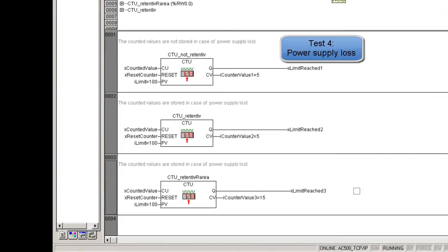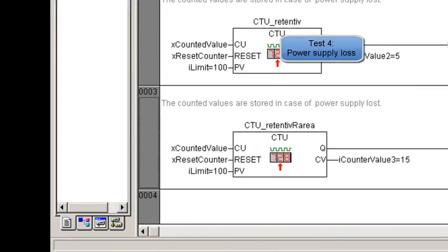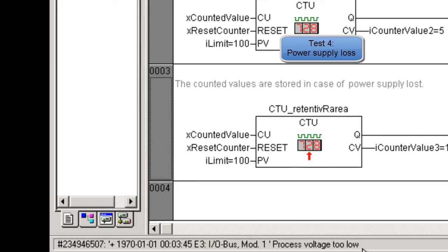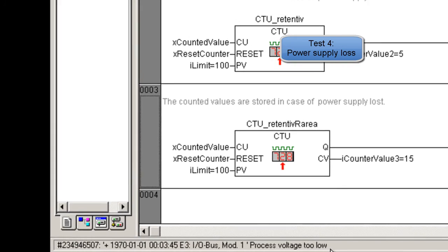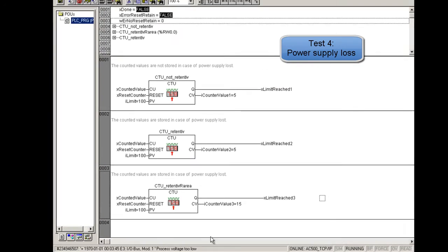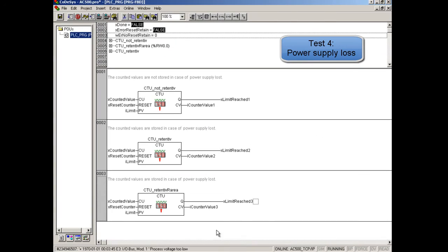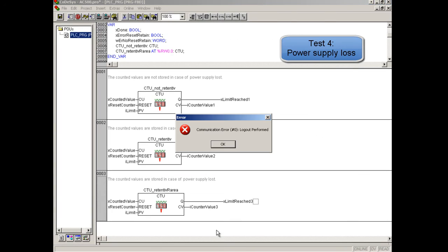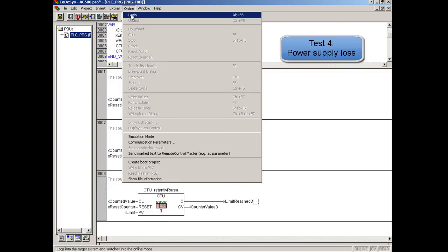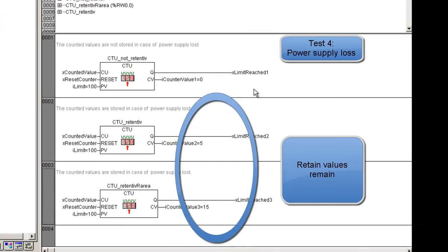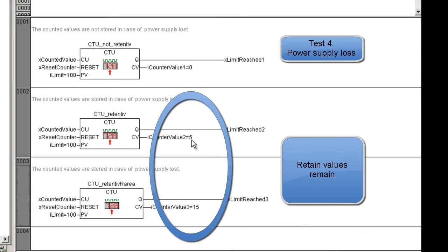Let us switch off the power supply of the CPU. The communication error is occurring because the controller is off and the connection got lost. We switch the power supply again and we log in the controller. We recognize that power supply off is initializing the not buffered values. All retained values remain.